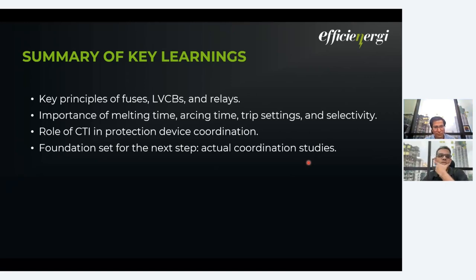We have a question that has come in. Can we minimize the inrush tripping, and what are the technical reasons for inrush? So Prasad, do you want to take that? Okay, one second. Is it possible to minimize inrush? Yes, inrush can be minimized. If you see the basic equation of inrush, if you start at the voltage peak of the supply, then you will have minimum inrush, because the magnetic flux always lags 90 degrees behind the voltage. Hitachi or Alstom have a different kind of breakers which close at the peak crossing. So that can be done.